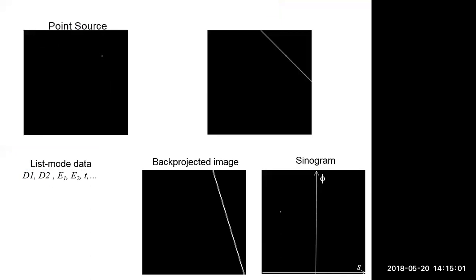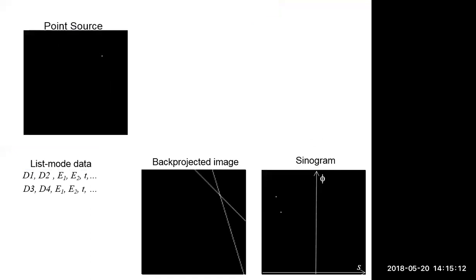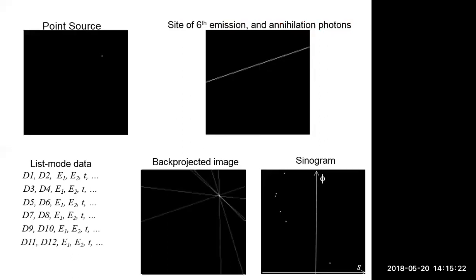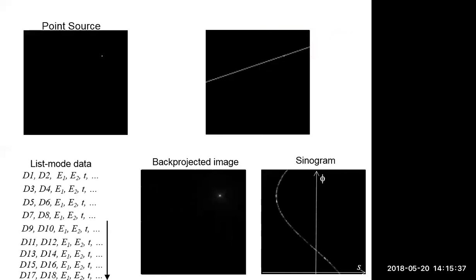We repeat this process: each new event gives another S-phi coordinate, adding a count in the sinogram and a line in the back-projection. After six back-to-back photon pairs, we have six counts in the sinogram and six intersecting lines. After 1000 events, you can see why a sinogram is called a sinogram — a point source corresponds to a sine wave on the sinogram. The back-projected image is a nice 1/r distribution, and we have 1000 list-mode events.